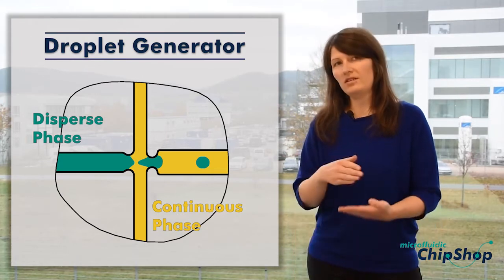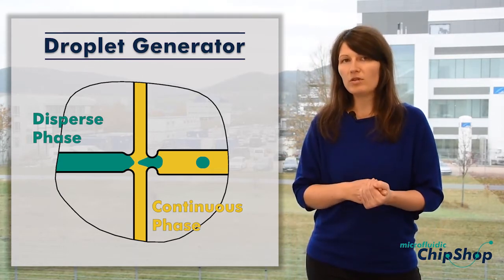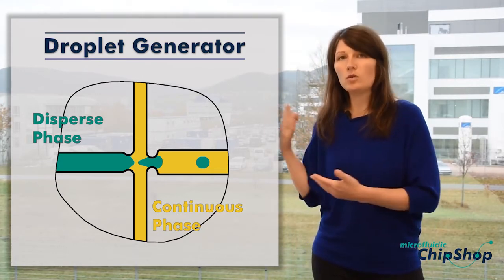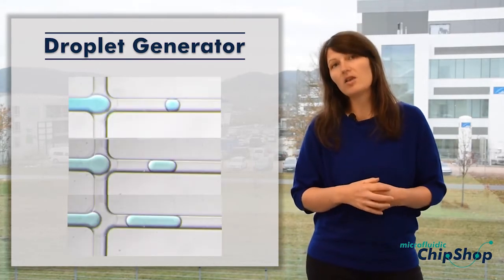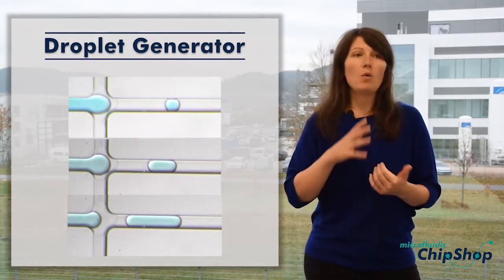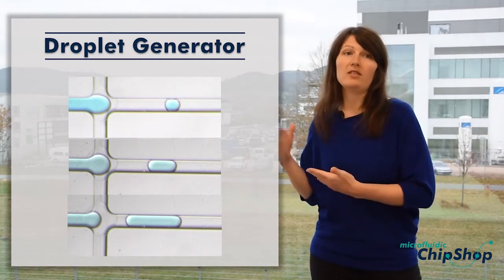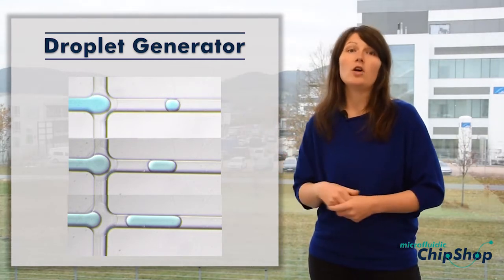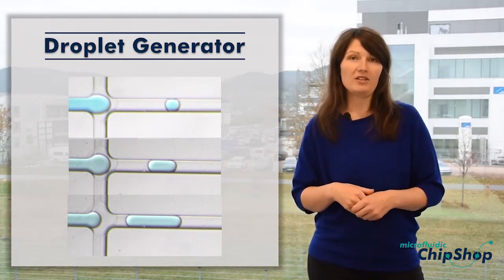The nozzle size and the ratio of the two phases — the sample phase, the dispersed phase, to the continuous phase — will define the size of the droplet, while the flow rates of the two phases will define the throughput of the entire droplet system.